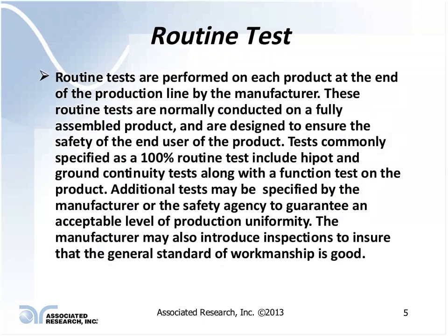Okay, the routine production line test, on the other hand, is something that we would do on all 100% of the products that we manufacture. And these tests are typically done when the product is fully assembled. It's done at the end of the production line.